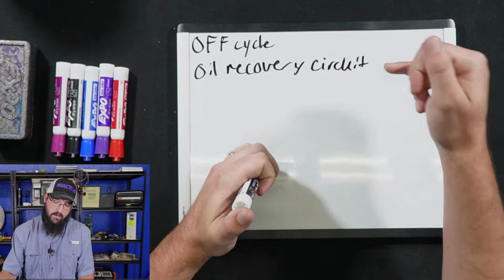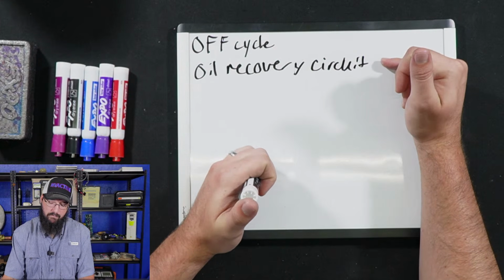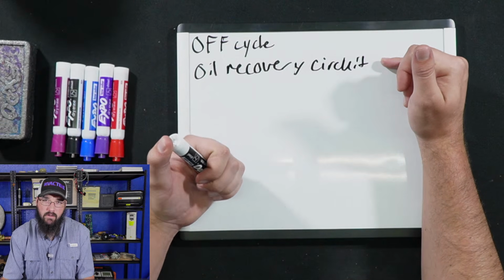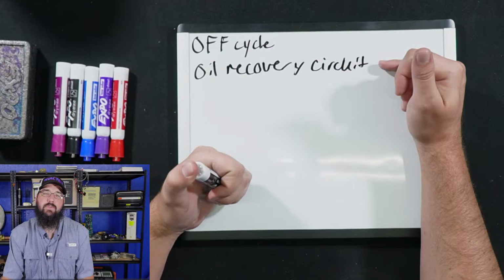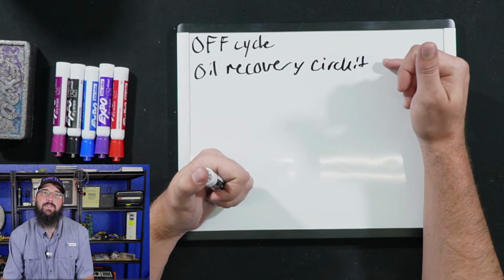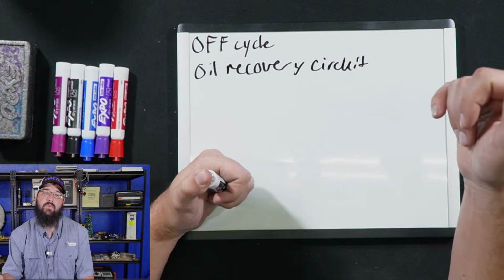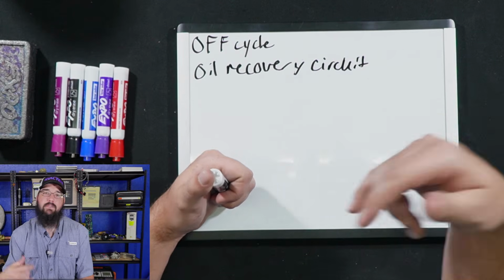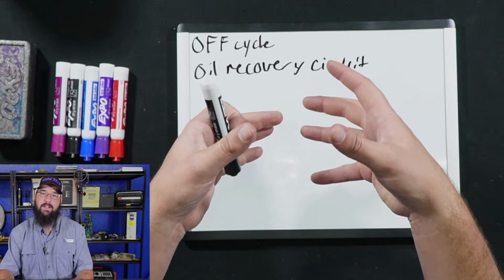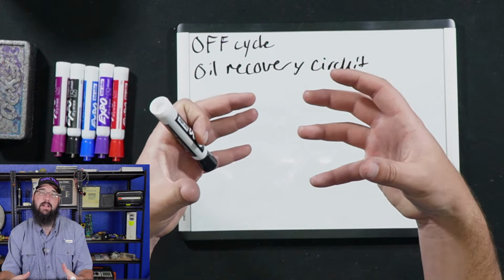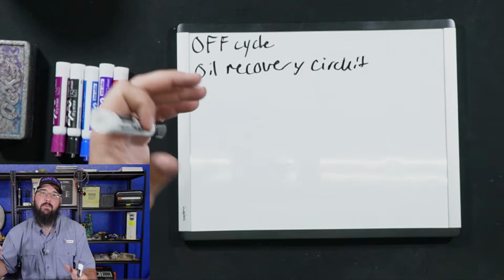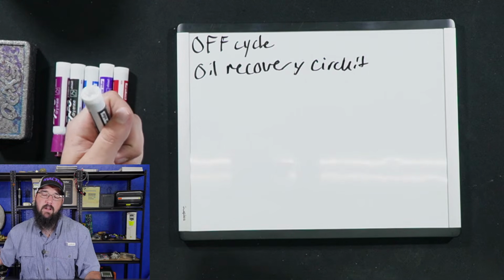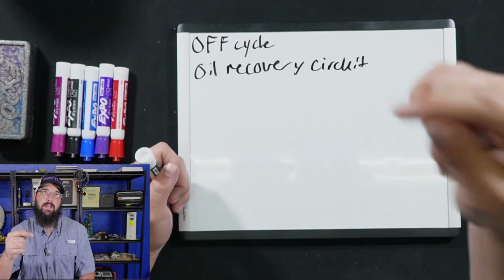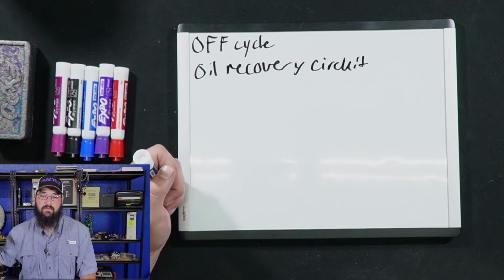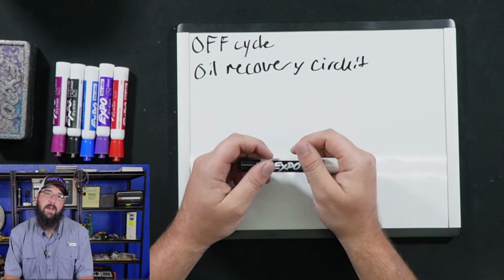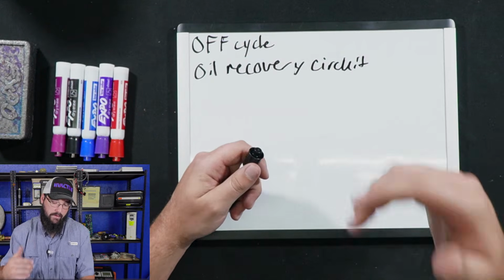Anyway, we could also use what Trane calls a gas pump. They've also started using a gas pump style setup on their air-cooled lines. So on the newer Trane air-cooleds, they've got a gas pump type assembly with a little heat exchanger where it collects the oil in the bottom of it. We open a hot gas bypass valve or discharge gas valve, not bypass, but discharge gas valve, and it sends that oil back into the compressor that way.